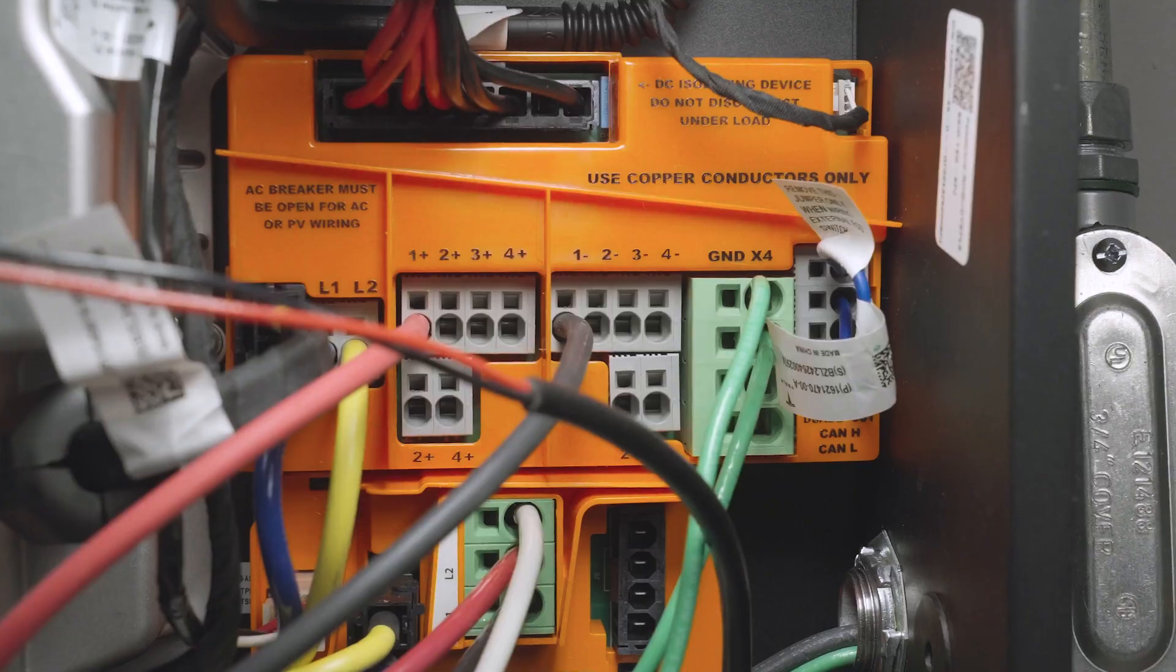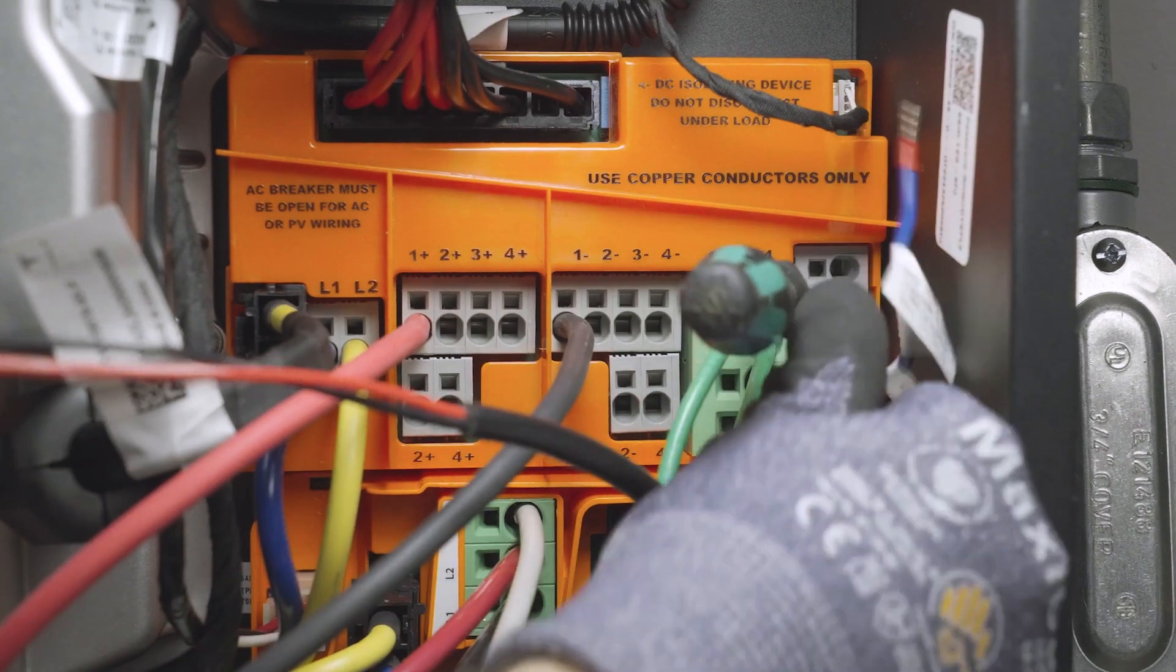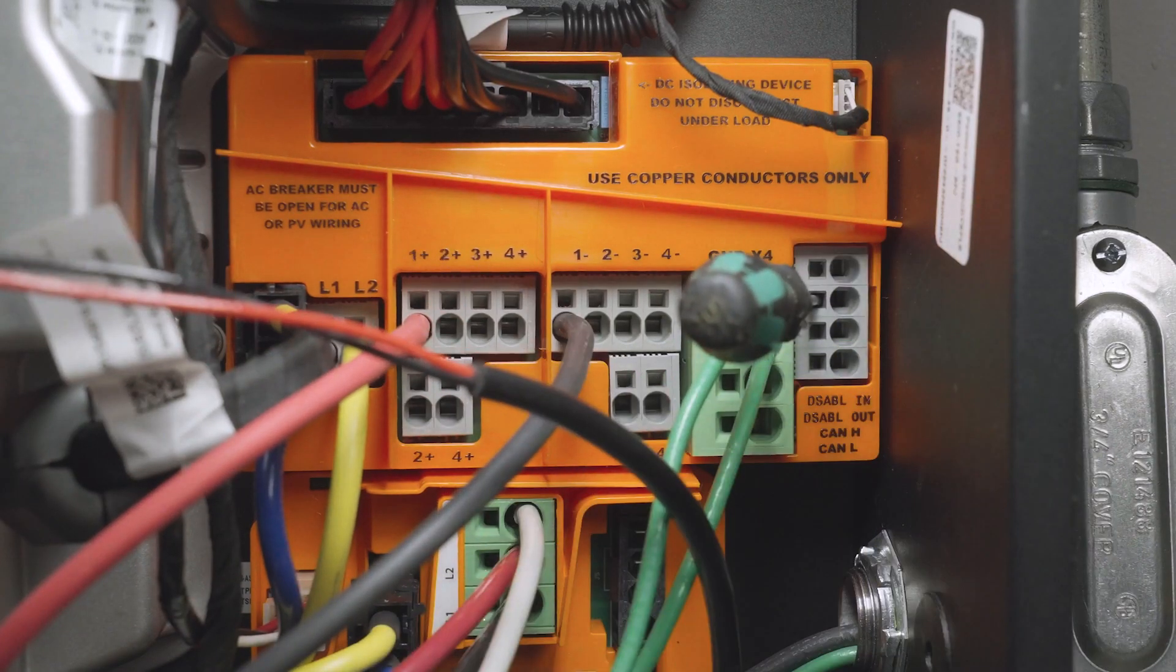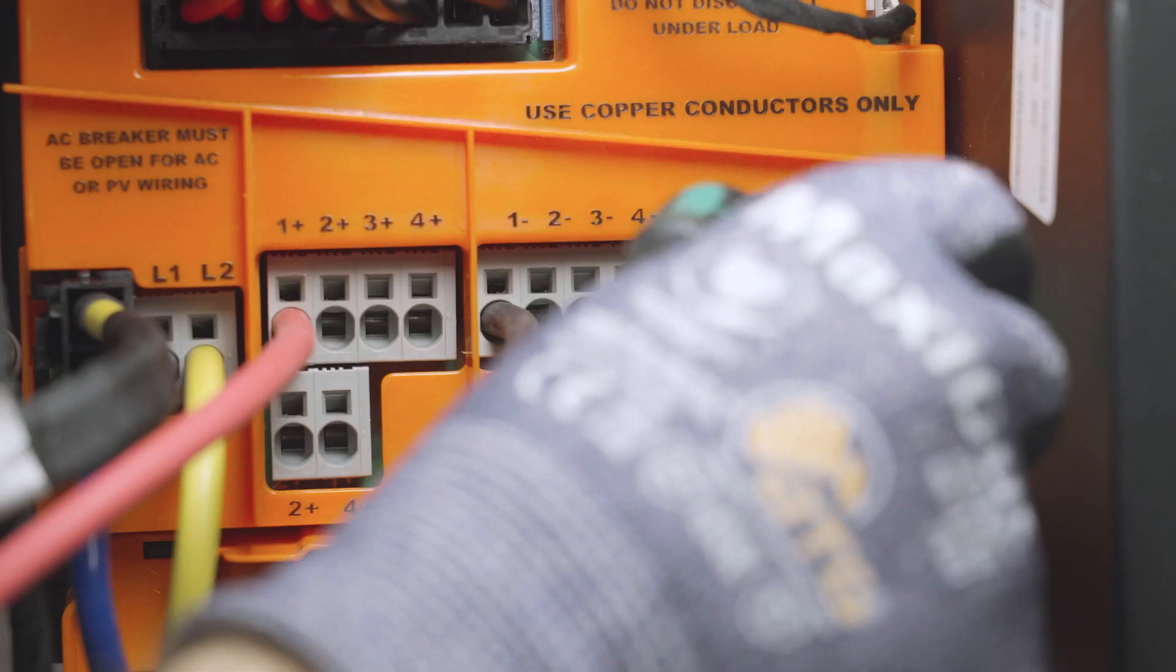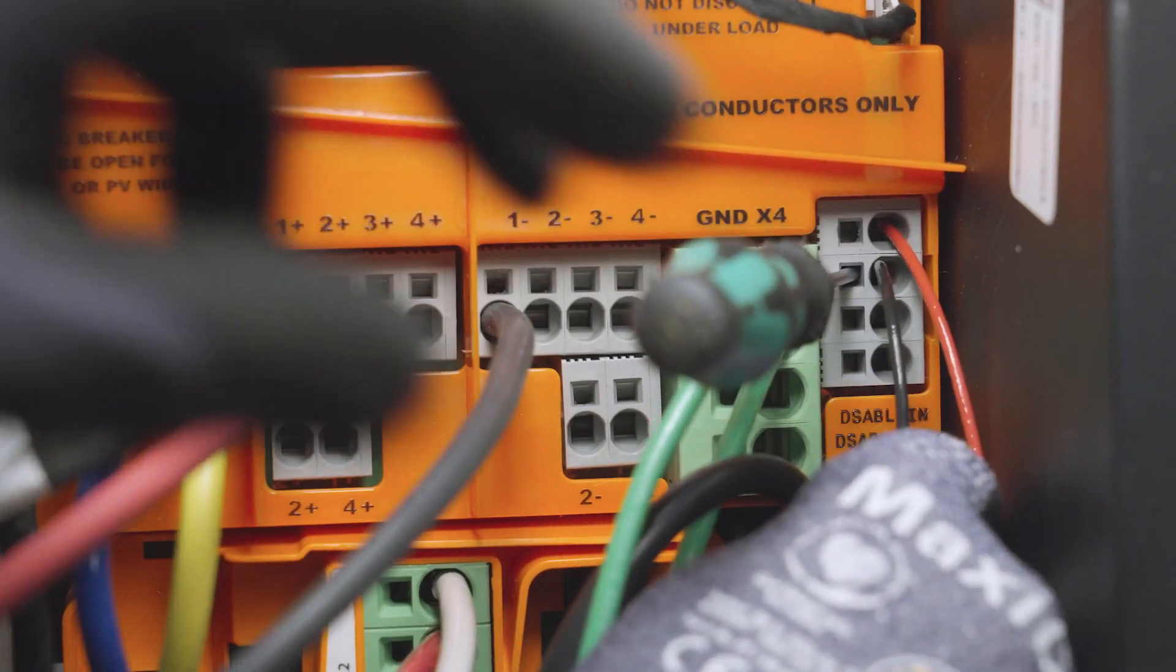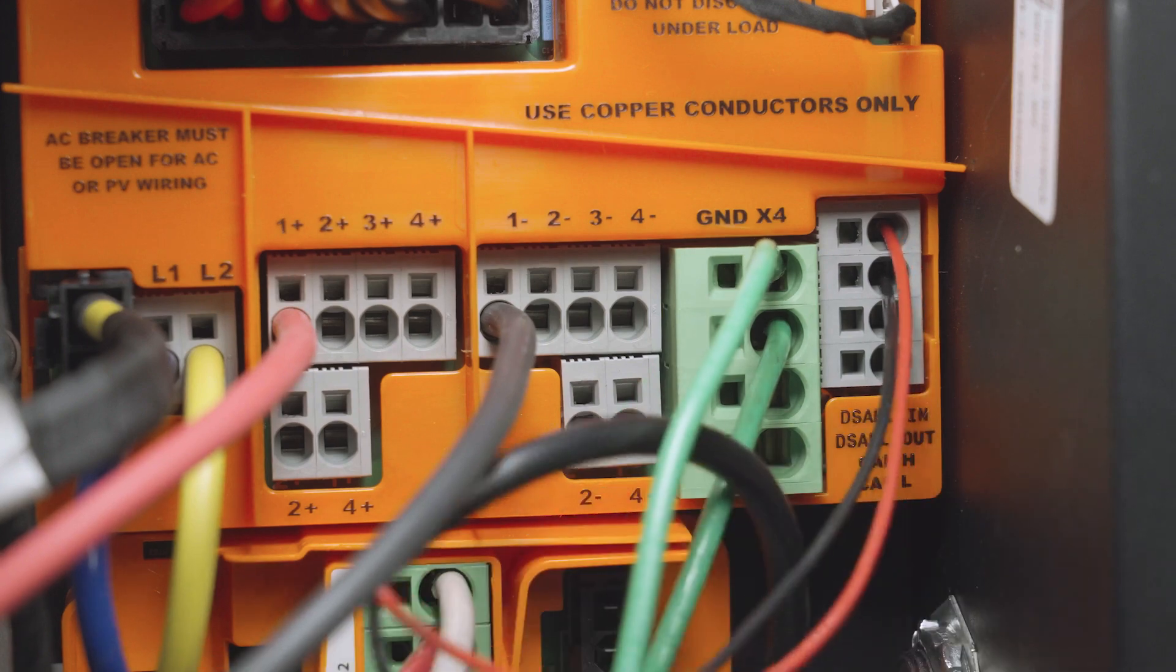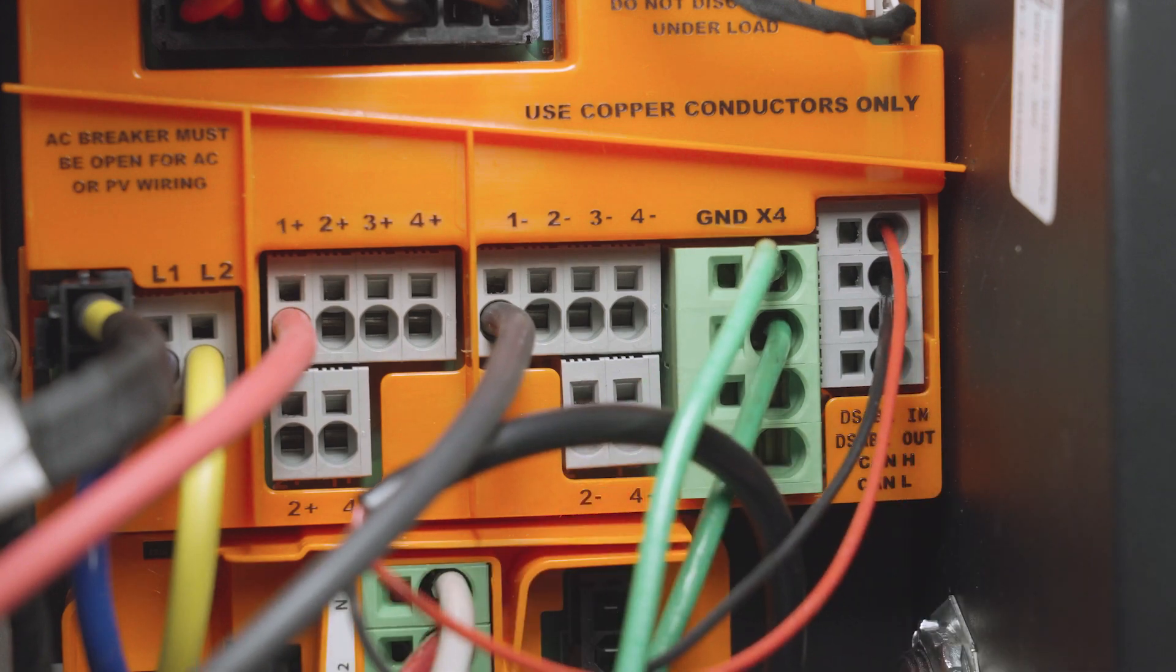Install wiring to connect these two terminals to the contacts of a normally closed switch rated for at least 12 volts and 1 amp. This switch must be installed externally in a readily accessible location near the utility meter.